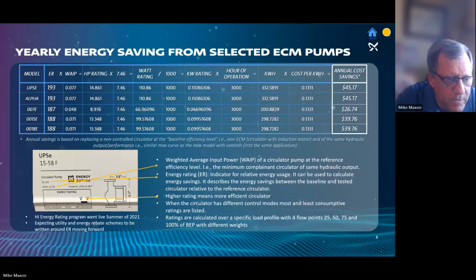The highest energy rating, it's rated at 193, which is the highest rating that Hydraulic Institute has given to any pump this size. And that will be listed on the box. This label that Hydraulic Institute has developed will be on the box. They have this calculation, the Hydraulic Institute does, using the ER, the energy rating that the pump has, the WAIP, which is the weighted average input power. And it goes through this calculation.